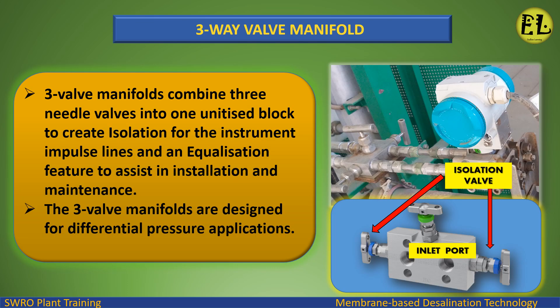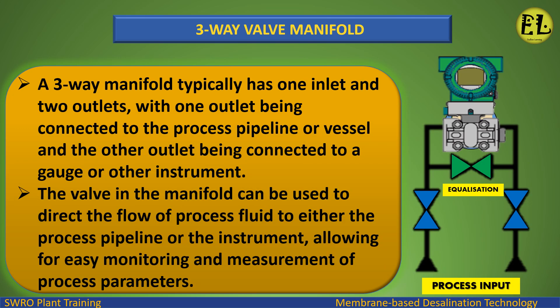Three-way valve manifold: three-valve manifolds combine three needle valves into one manifold block to create isolation for the instrument impulse lines and an equalization feature to assist in installation and maintenance. The three-valve manifolds are designed for differential pressure applications. A three-way manifold typically has one inlet and two outlets, with one outlet connected to the process pipeline or vessel and the other connected to a gauge or other instrument. The valve in the manifold can be used to direct the flow of process fluid to either the process pipeline or the instrument, allowing for easy monitoring and measurement of process parameters.